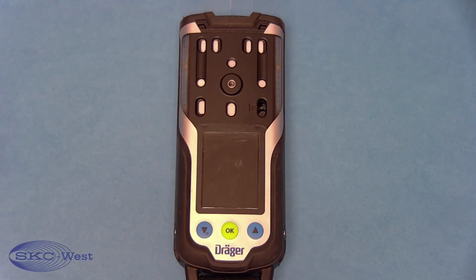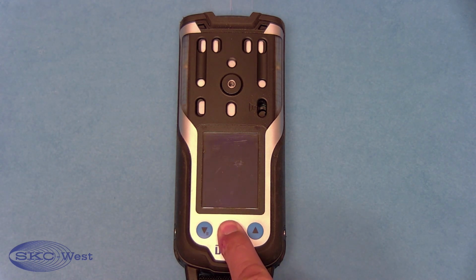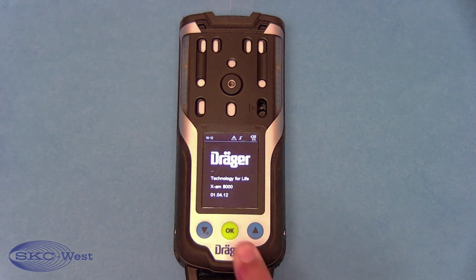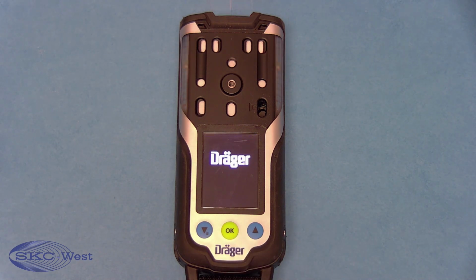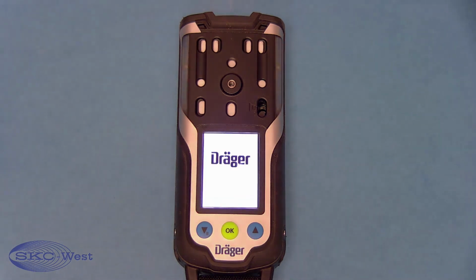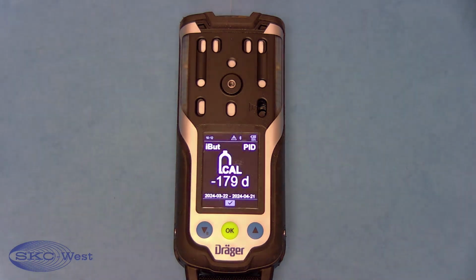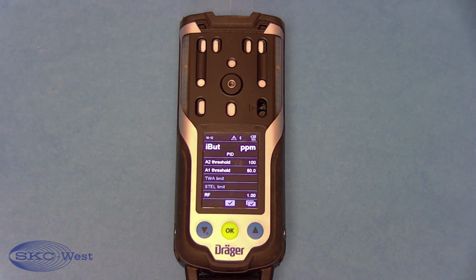To turn on, hold down the green OK button for approximately 3 seconds. The monitor will briefly alarm, then display various information as the monitor warms up. If you have multiple monitors for bump testing, the process will be accelerated if you start them all up before proceeding to the bump test or calibration procedure, whether done manually or preferably on the X-Dock docking station.